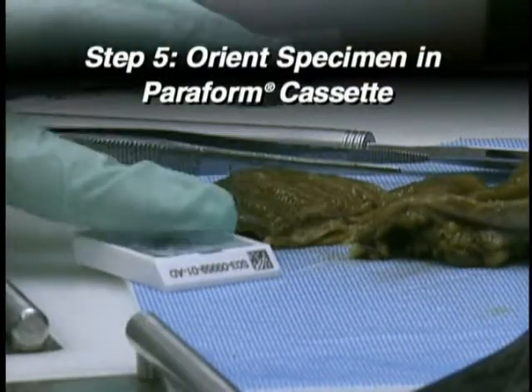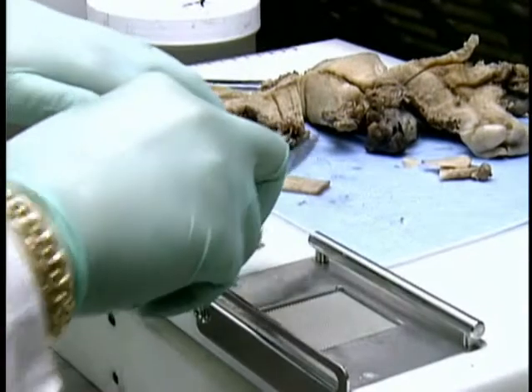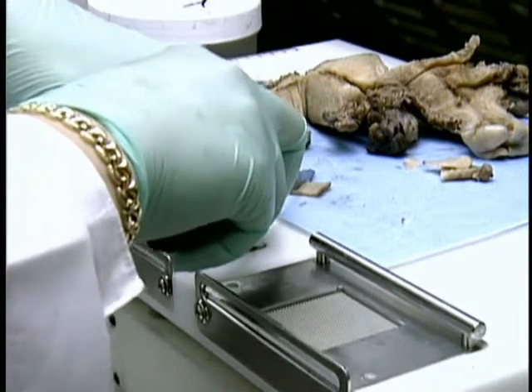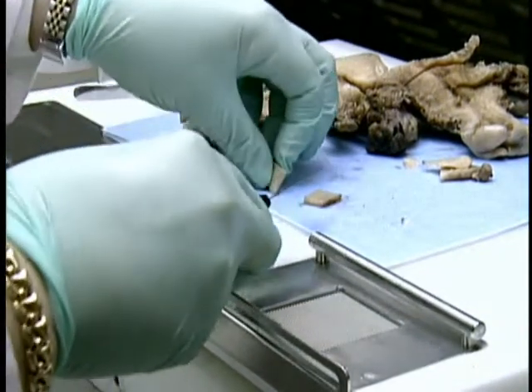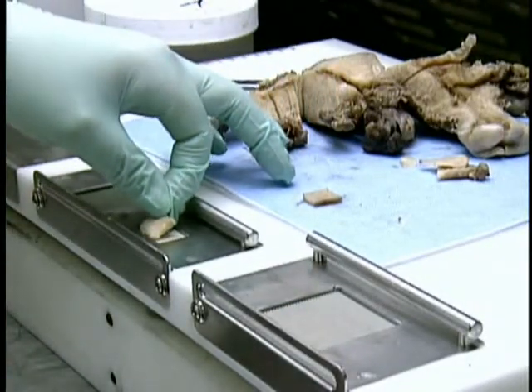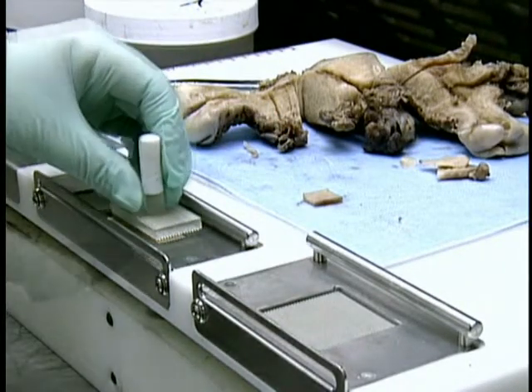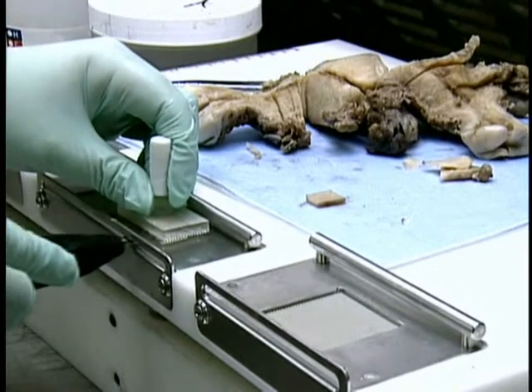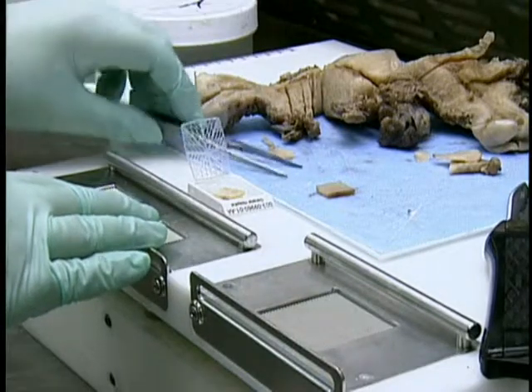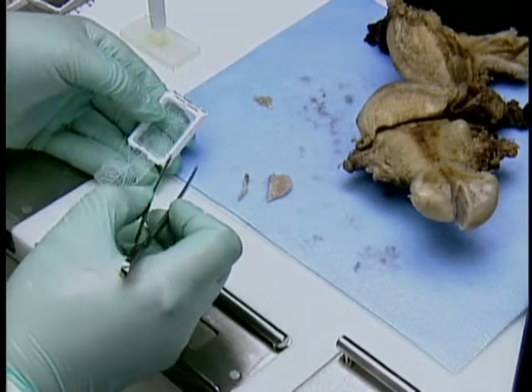In the final step, the specimen is oriented in a Tissue-Tek paraform sectionable cassette for processing. These steps also apply in other cases, such as when a larger specimen is necessary. Here, a section of this uterus requires examination. A section is cut and placed in a well on the grossing board, which has already been adjusted for use. A tamping tool is used to hold the tissue in place as the surface is cut to the appropriate thickness. Once finished, the specimen is then oriented in a paraform cassette. Ideally, the cassette should be labeled prior to sample placement for easy identification.